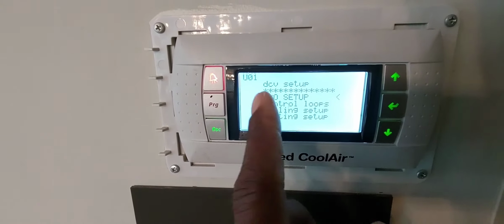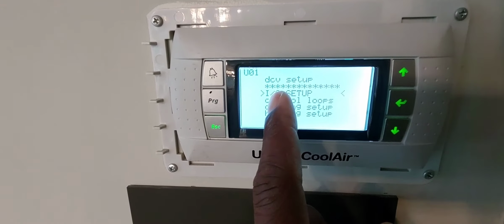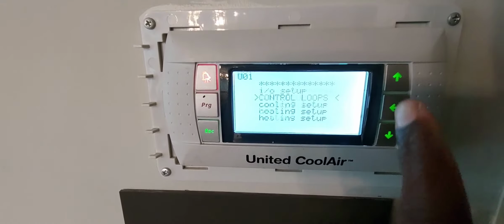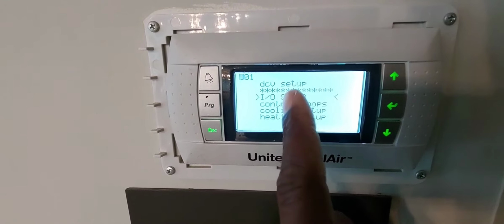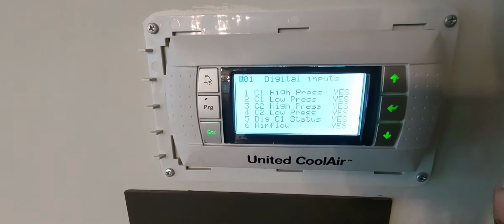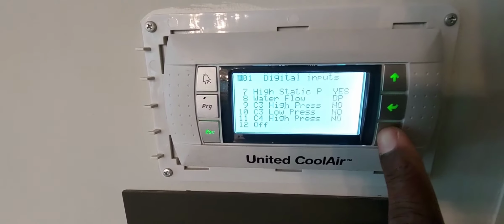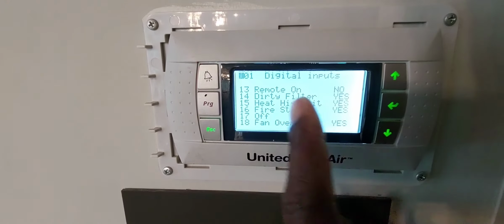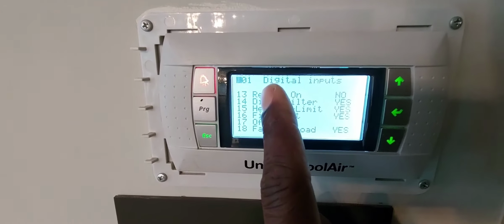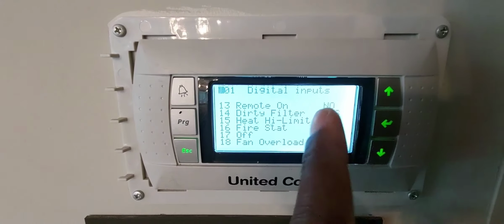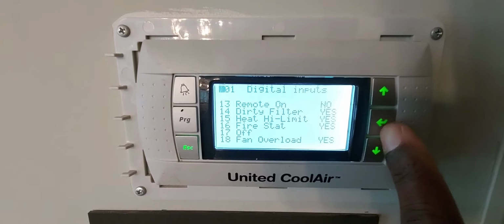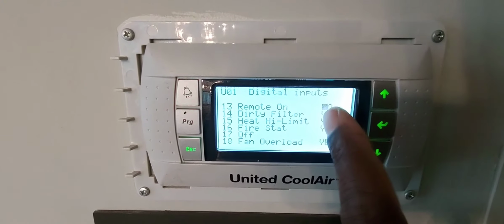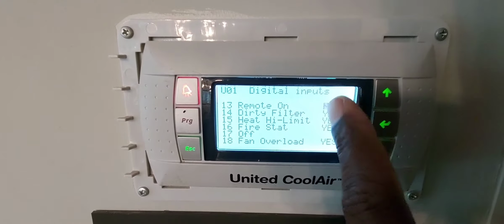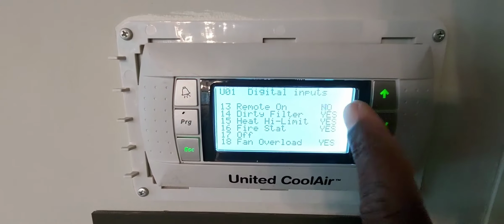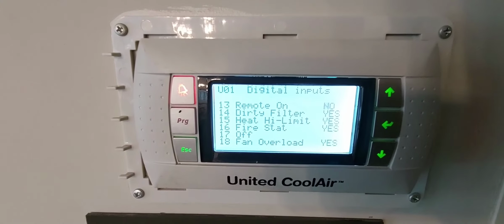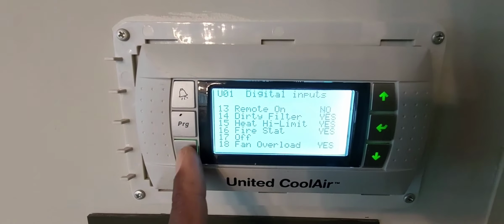So we're going to scroll down to IO setup, press enter on that, and scroll down to remote on and off, remote on. Currently the option is no. You press the enter key, make the cursor go on the same line, and you see it's flashing over there - no.